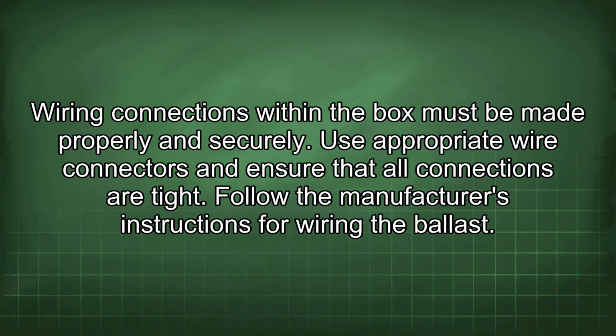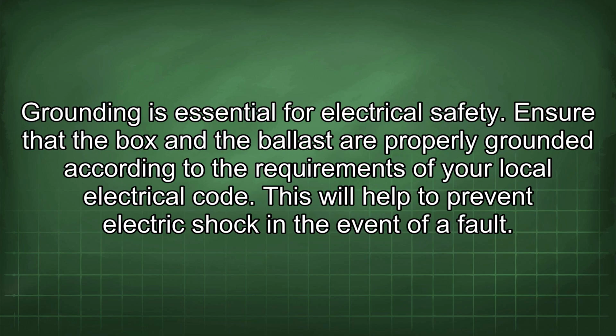Wiring connections within the box must be made properly and securely. Use appropriate wire connectors and ensure that all connections are tight. Follow the manufacturer's instructions for wiring the ballast. Grounding is essential for electrical safety. Ensure that the box and the ballast are properly grounded according to the requirements of your local electrical code. This will help to prevent electric shock in the event of a fault.